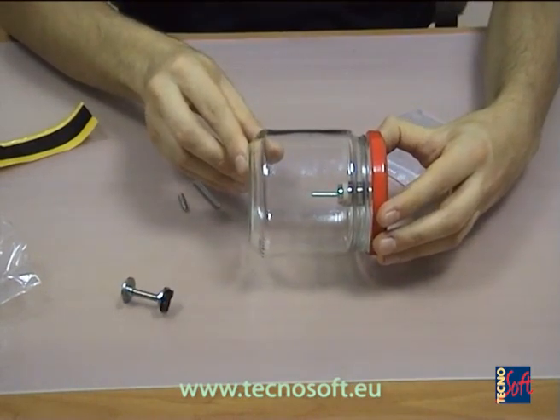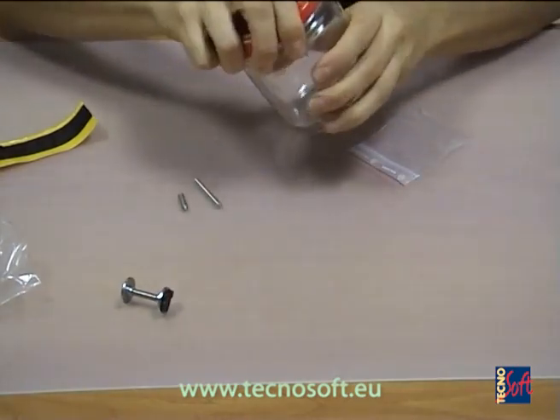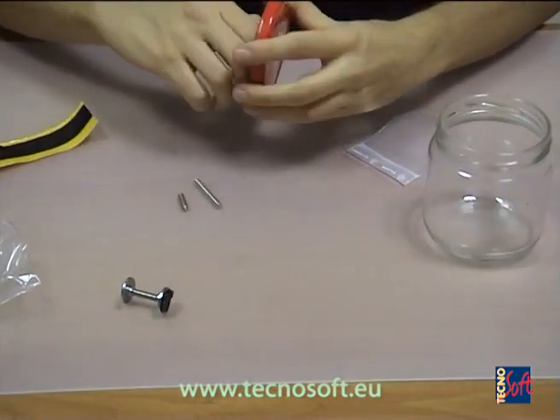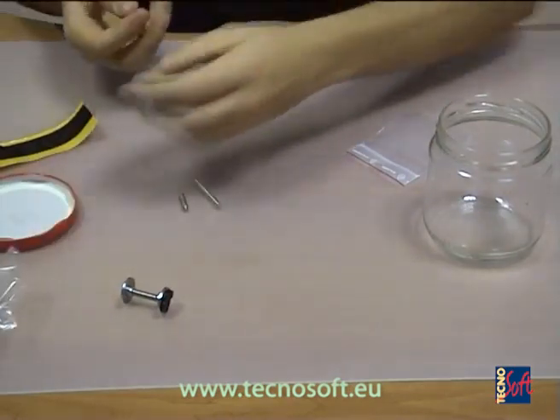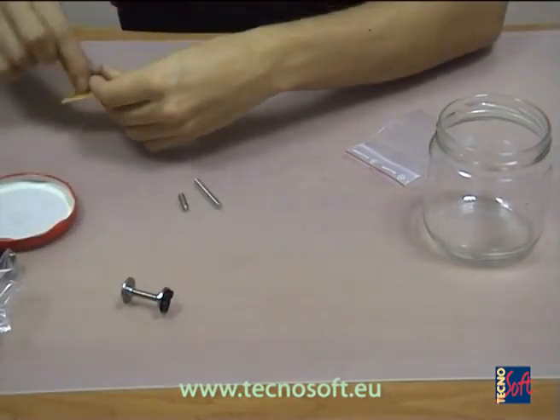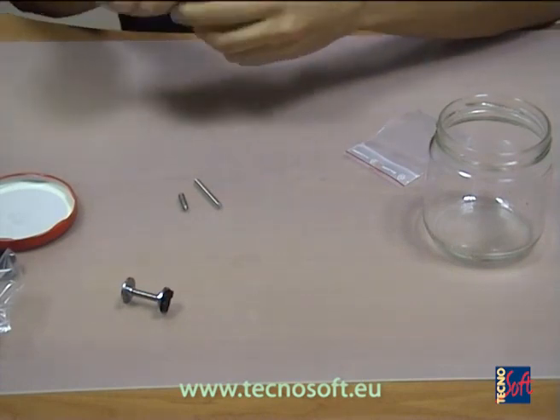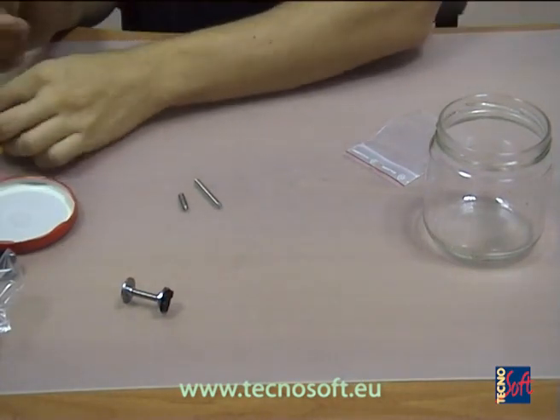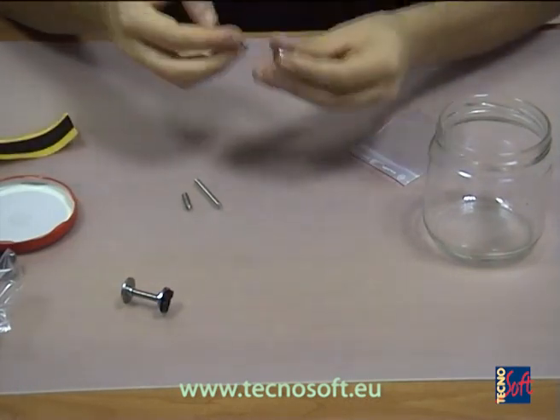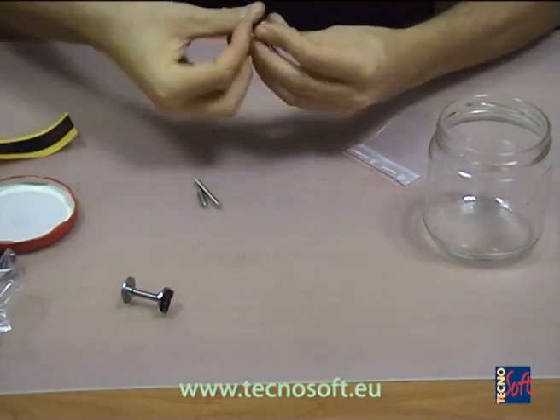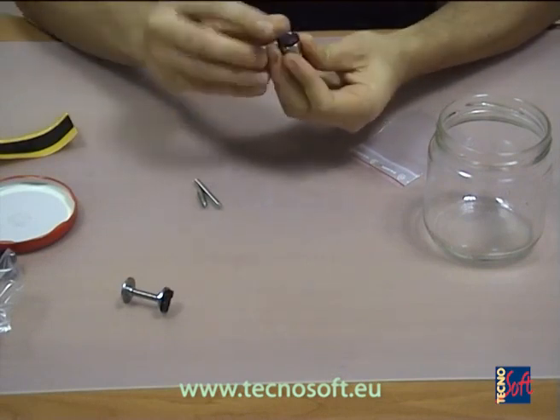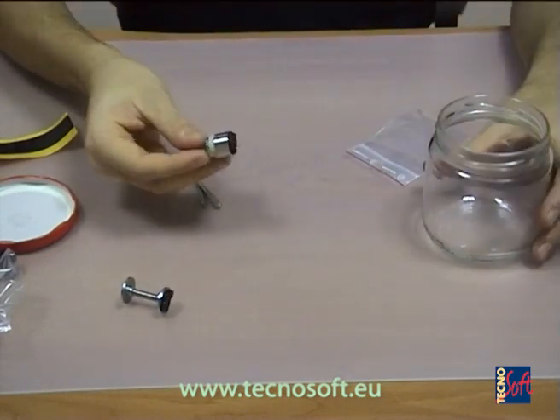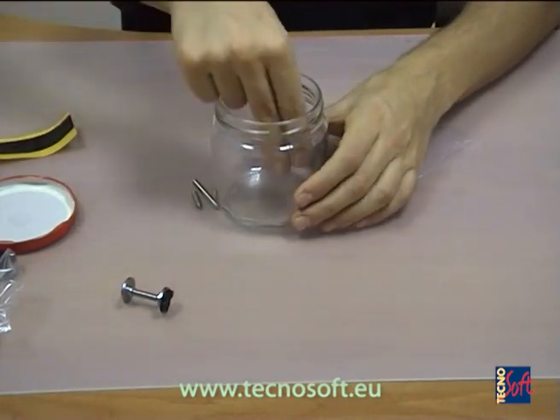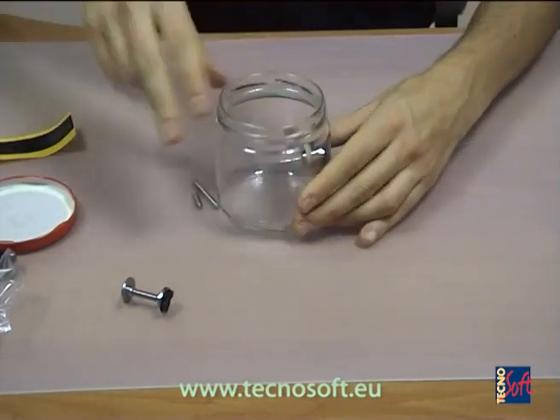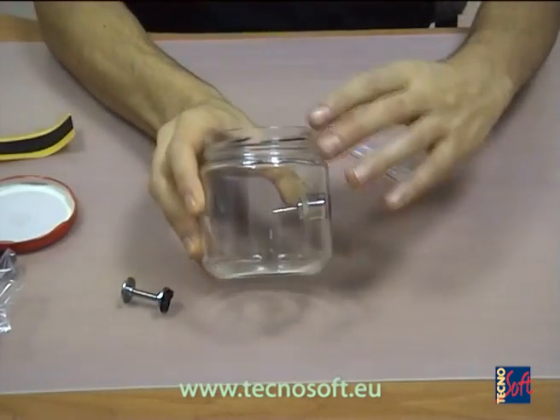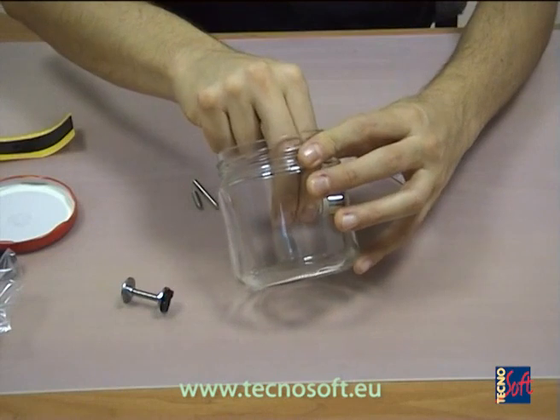Of course, you can use the rubber without the base directly on the logger, and in this case we can mount it on the vertical wall of the jar itself. We place some adhesive rubber on the base of the logger and we press it tight on the vertical wall of the jar. You can eventually adjust its position to place the tip of the probe at the center.